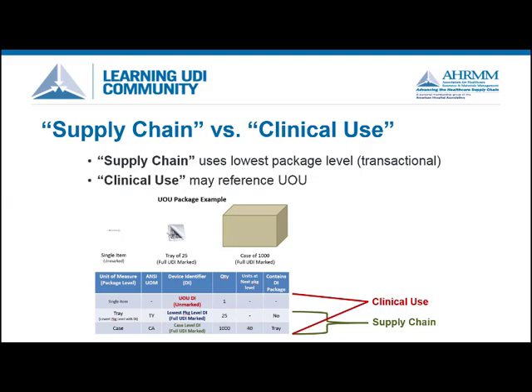This is especially true for sterile products, since removing the product from a package renders it non-sterile. This lowest package level, or base unit, generally allows device manufacturers to print the physical barcode to identify the product. In instances where the lowest package level contains multiple items, there may be a need to extend product information down to the individual unpackaged item. In this example, we may need to identify the individual syringe as opposed to the full tray. This is why the clinical use of the UOU may extend to a larger range of device identifiers than the supply chain.